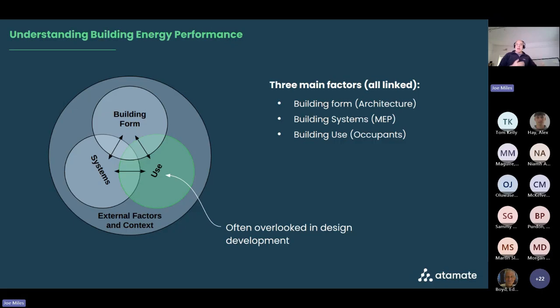It's very easy to collect data on that. Typically we've turned down the existing BMS, which at this stage is controlling the boilers, looked at the flow temperatures, reduced them, and measured to see if it's capable. Clearly, if the space can't get to temperature at 55-degree flow temperatures, then you're looking at a complete retrofit of your heating system.